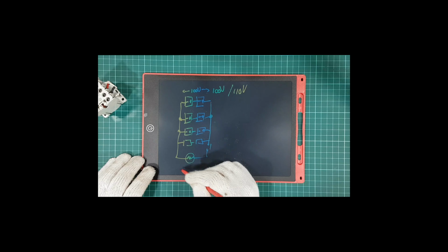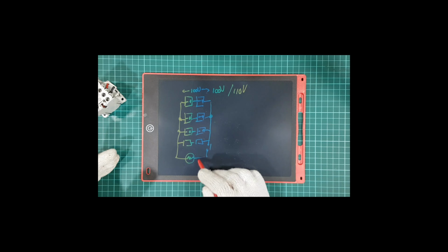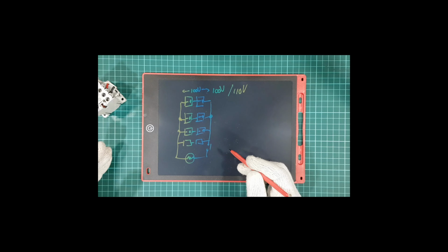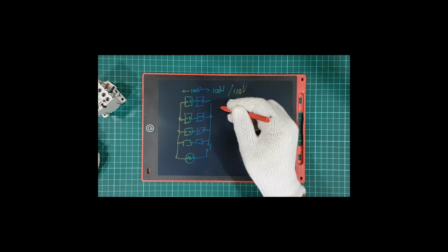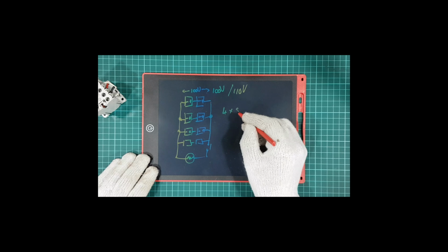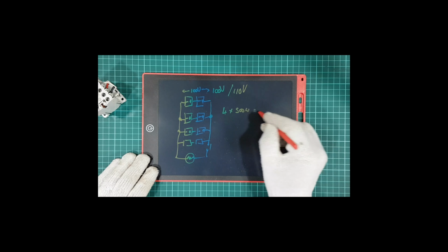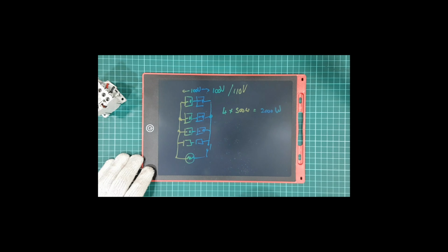If you're only warming your water, then you can match the panels with the kilowatt rating of your geyser. So if you want a 2 kilowatt geyser, you will need 4 panels. If they are 500 watts, that's 4 times 500 watt will give you your 2000 watt that you need to heat up your geyser.